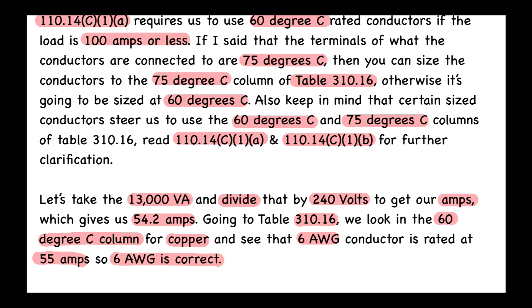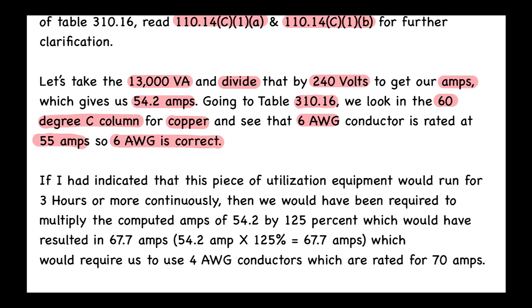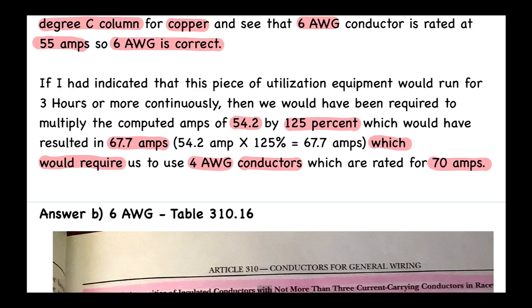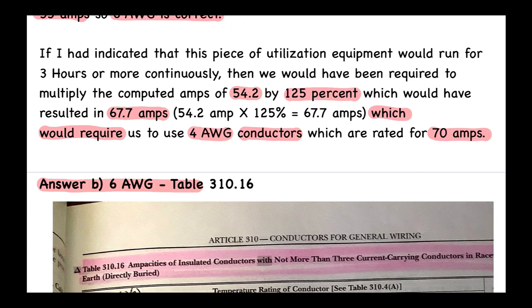If this equipment were to run continuously for three hours or more, we would be required to multiply the 54.2 amps by 125%, resulting in 67.7 amps. That would require a 4 AWG conductor, which is rated for 70 amps. But since it's non-continuous, the answer remains B — 6 AWG.